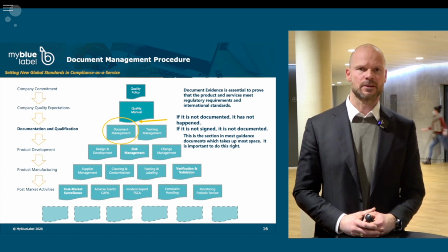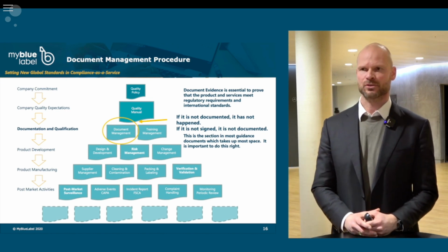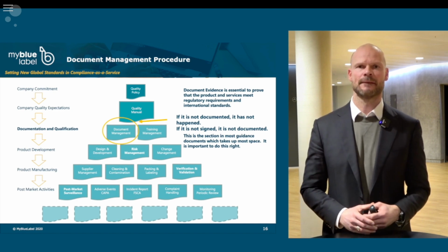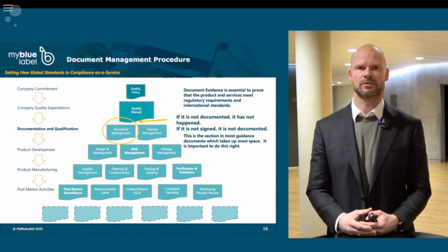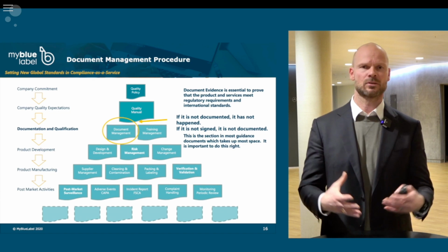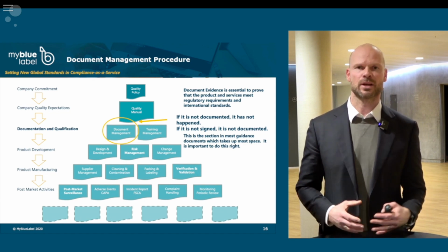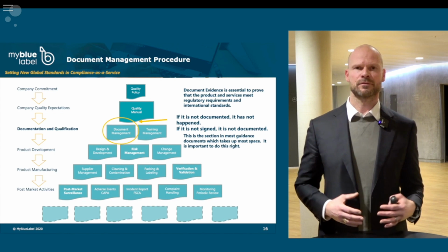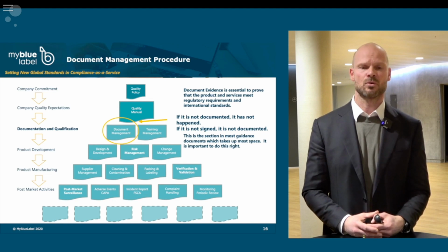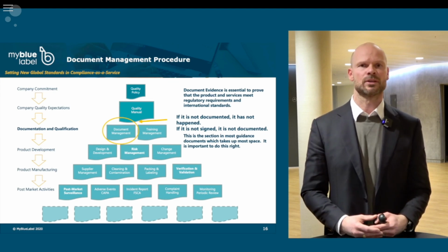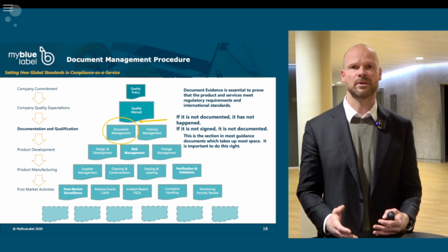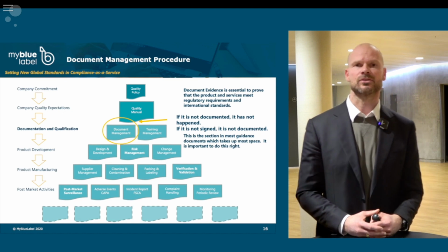Going to the next level here is where I find it's the most important focus area: documentation. Documentation is the source of information where you can provide documented evidence that your device is working as intended. And if the information that you have provided is not documented, then the auditor will not know that your product is safe. So there are some general rules: if it's not documented, it has not happened. And if it's not signed, then it's not documented.